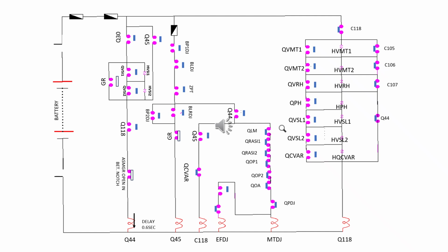Okay, today I'll describe step by step how the relay energizes and closes the locomotive circuit breaker, DJ or VCB. This is its control circuit, because VCB is on the 25 kV side, but we cannot work directly on the 25 kV side. So we are using a 110 volt DC circuit with an electromagnetic and electro-pneumatic circuit to avoid hazard. So now see, when I close the battery switch, the supply is received.